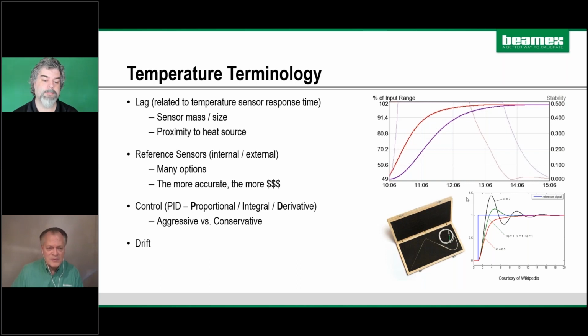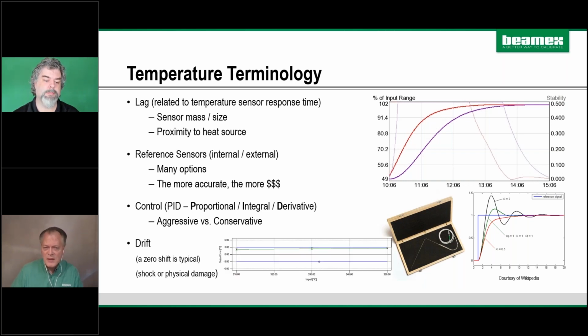And then finally, we want to talk about drift, since we're talking about calibration. How do sensors drift? Typically, it's normal to see a zero shift. This is due to the sensor experiencing some kind of shock, or extremely high temperatures, or if it's in a pipe with fluid going by, it could get bumped around, and it's going to cause most likely a zero shift.